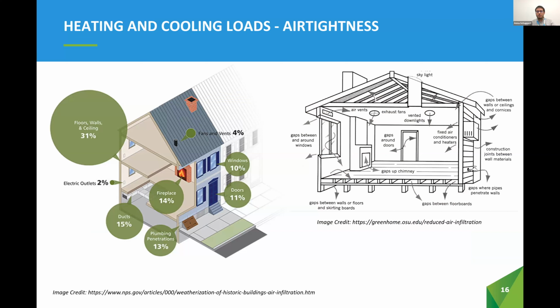Air leakage is one of the important load components shown on the previous slide, and we can see here many of the most common areas for air leakage. In particular, transitions and joints between the different assemblies, such as walls to floor and roof, or windows and doors to their parent wall, are common areas of air leakage. Similarly, mechanical, electrical, and plumbing penetrations require careful design and detailing.